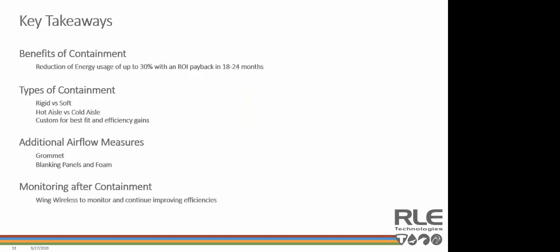So, in conclusion, I wanted to talk about the key takeaways from today's presentation. With containment, you can realize a reduction of energy usage of up to 30% and realize an ROI in 18 to 24 months. Soft containment is generally less expensive than rigid containment, but doesn't look as aesthetically pleasing, and it can also be less effective at containing a space. As mentioned, if an aisle is overpressured or underpressured, the curtains can blow open and let the cold air and hot air mix. Rigid containment is typically more expensive, but looks more aesthetically pleasing, and it's more durable over time.